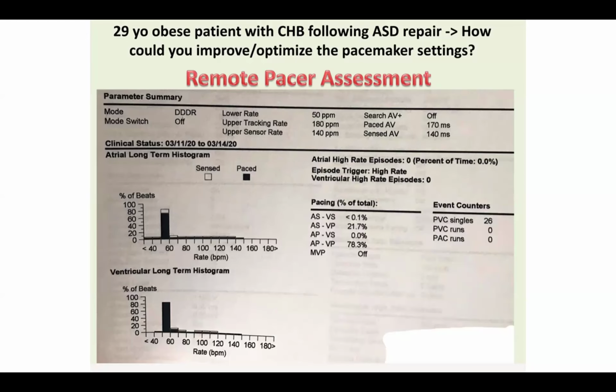Sorry, Dr. Pass, go ahead. Barty, sorry. What is the upper tracking rate and the upper sensor rate, if you can throw some light on that? Very good question. Thank you for asking. So the upper tracking rate is how high will the pacemaker follow the atrial rate? In other words, with this program of DDDR, if the atrial rate goes as high as 180 beats per minute, the device will track it, meaning it will pace the ventricle in concert to the atrial rate up to 180 beats per minute.